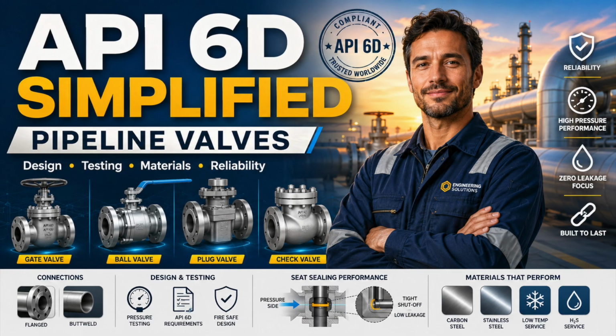The first question is not, what valve do I want? The first question is, what must this valve do? Does it need to isolate pressure, prevent reverse flow, permit pig passage, provide sectional isolation, support emergency shutdown, create double isolation, allow cavity venting, support maintenance, protect equipment during a transient, control inventory release, remain operable after years of inactivity? The valve is only the hardware selected to perform that function.